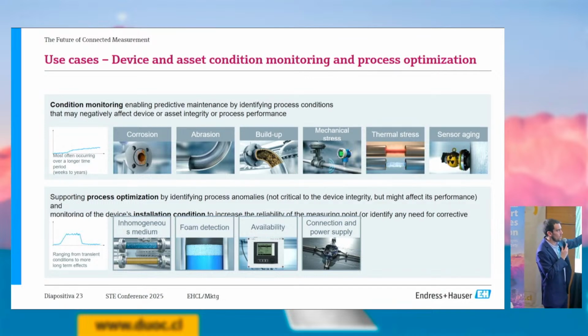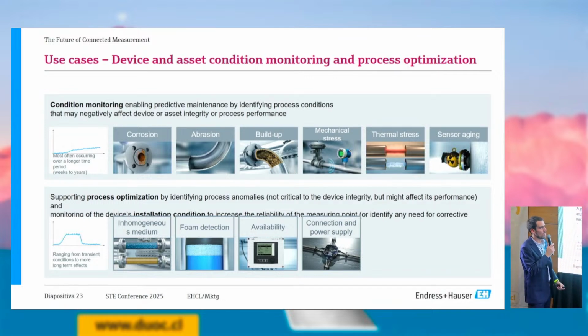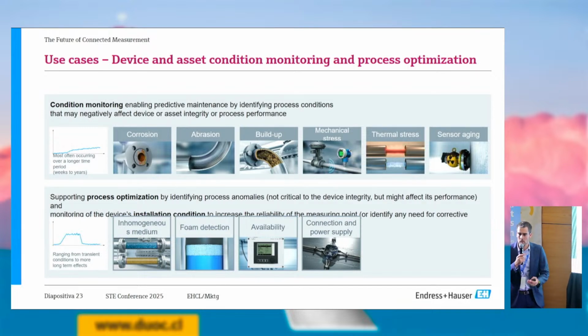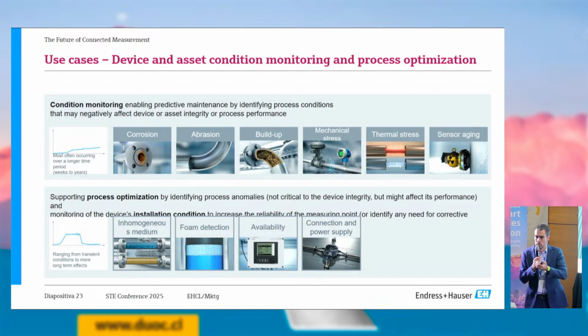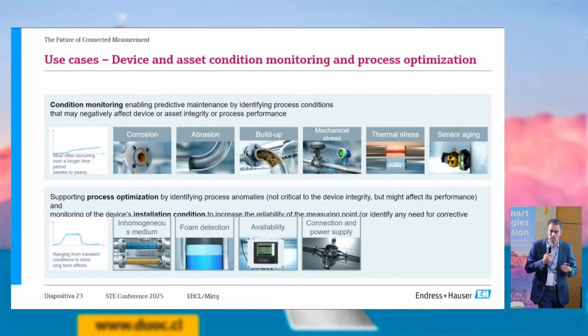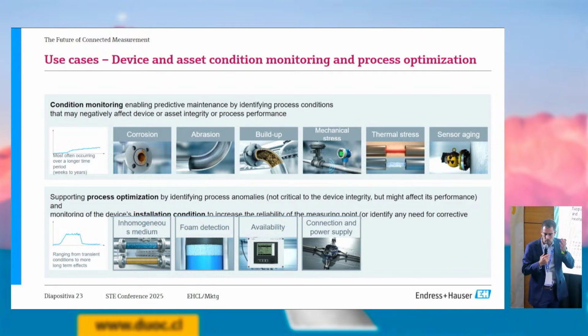Corrosion of the tube can be measured on a Coriolis, for example. Abrasion can be measured at the same time. Build-up on the face of a radar device, or in a mag meter, we can measure the amount of build-up generated, for example in a lithium plant, or a copper plant, or even a convenience food plant.